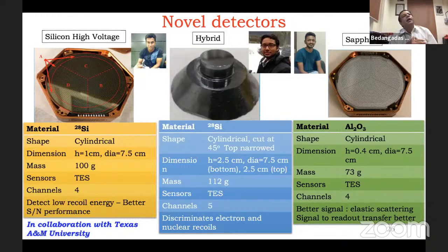This is done by a mechanism, the way we try to read out the signal, which on one side can be made as close to contact free as possible. The leakage current was tremendously reduced by two orders, I think to about 10 to the power minus 16 amperes or so, if I recollect correctly. That allowed this detector to operate, instead of at 70 volt, with a linearity of response up to 250 volt, and the resolution was also very good.